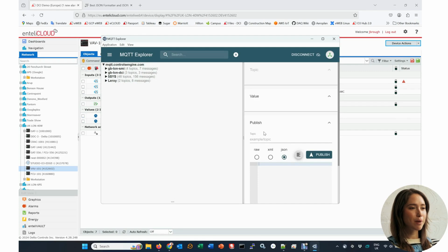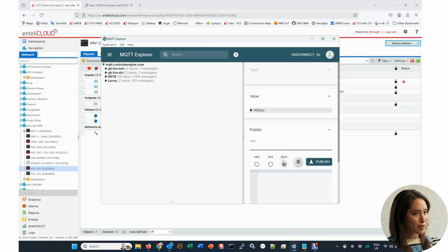We can do this by publishing to the topic from MQTT Explorer and making sure we have set the retain flag. Then whenever something subscribes to that topic, the broker publishes that retained message. I will do this now. The default topic prefix for UDMI is site reference /devices/device name. Then we add config to that and put the relevant data in the message payload.